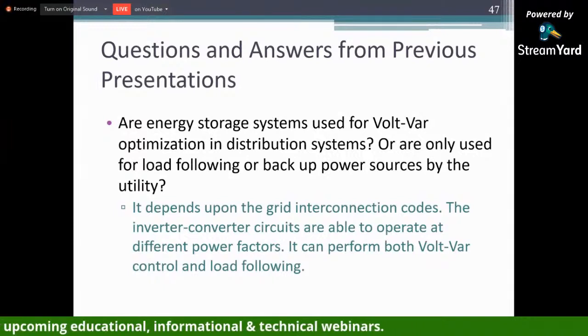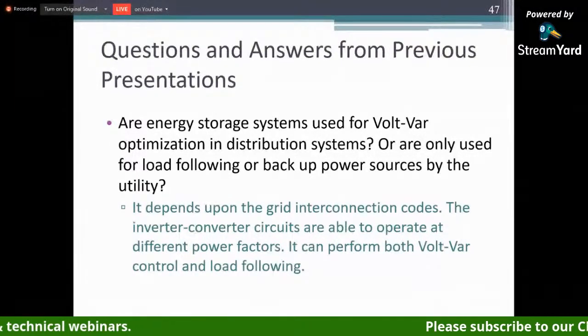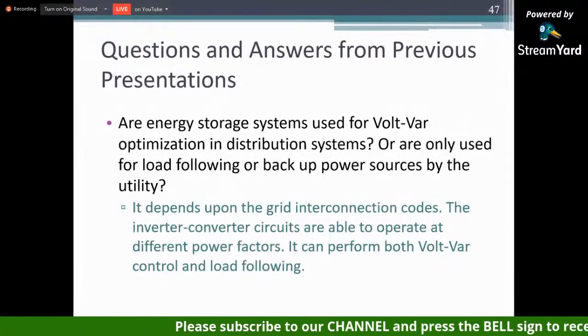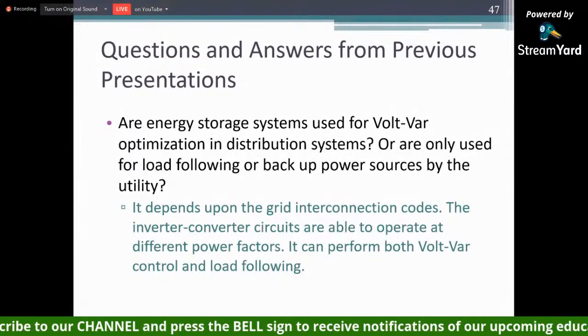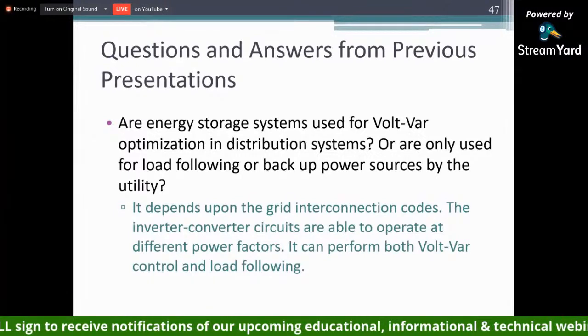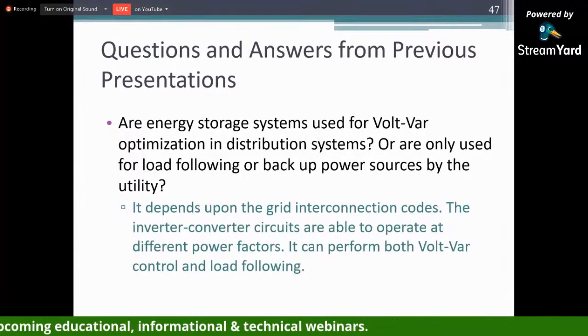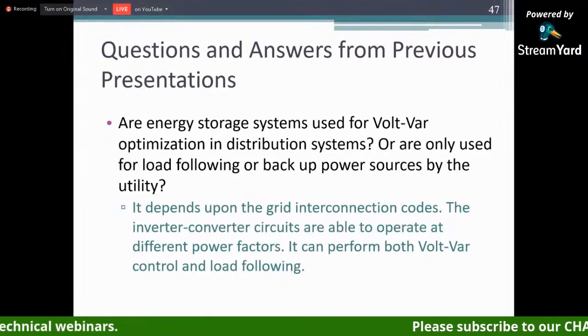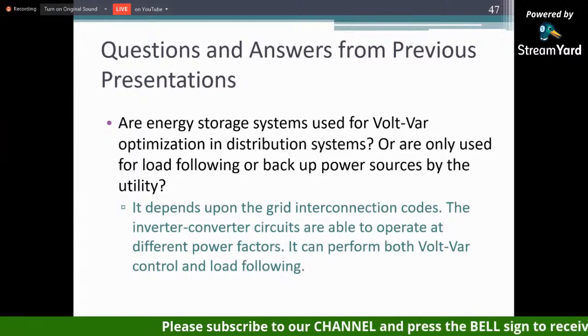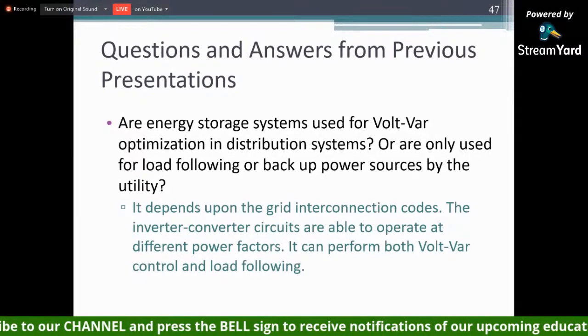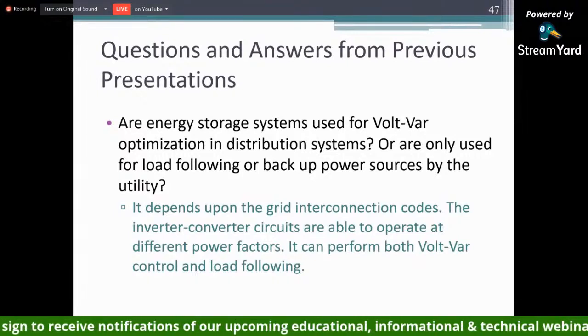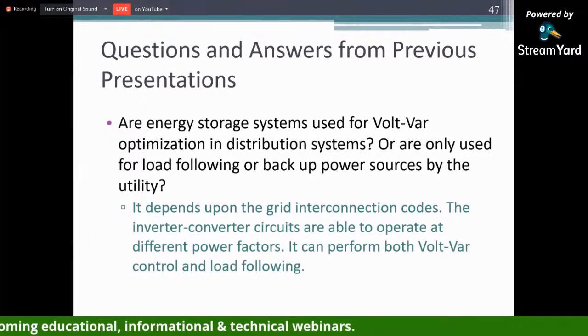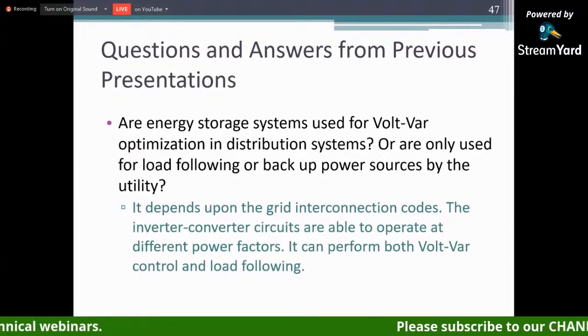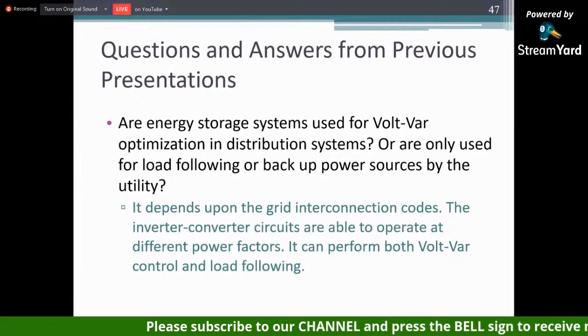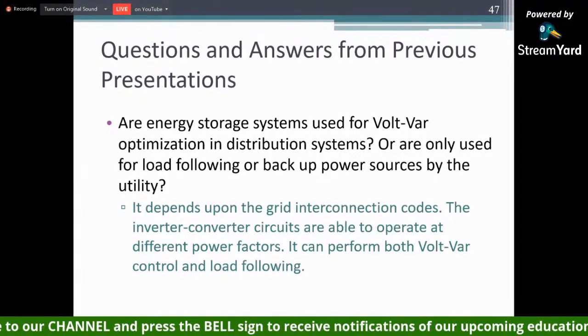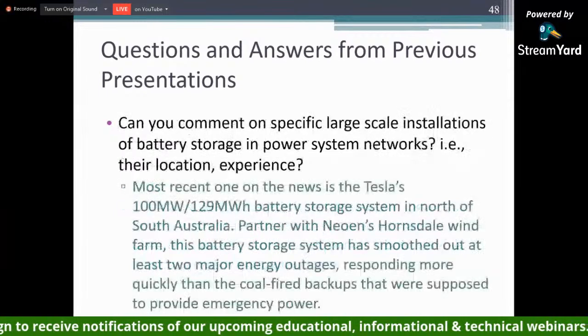They can also do voltage and VAR control. In the power electronics world, historically we do grid following, meaning we don't try to control the voltage and frequency of the system. But once you get into microgrids, or power electronics gets bigger, we try to do grid forming. If you do grid forming, you have to do volt control and frequency control. It really depends on the size, the application, and what ancillary service you're trying to participate in.